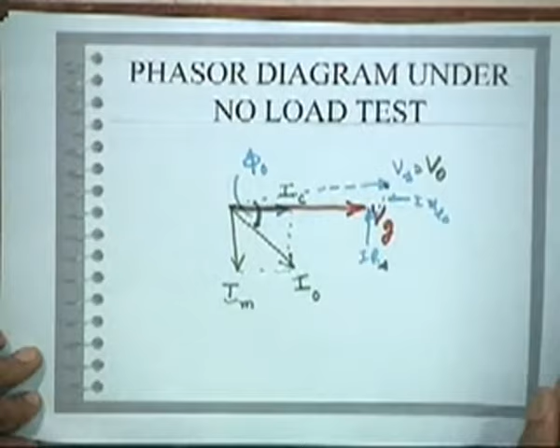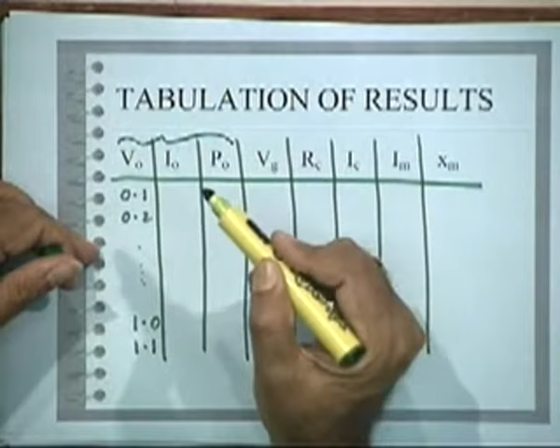What you are measuring is V naught, I naught, and P naught. V naught is varied from a small value to slightly above the rated value, then I naught and P naught are monitored. So these three are the measured readings from the test.